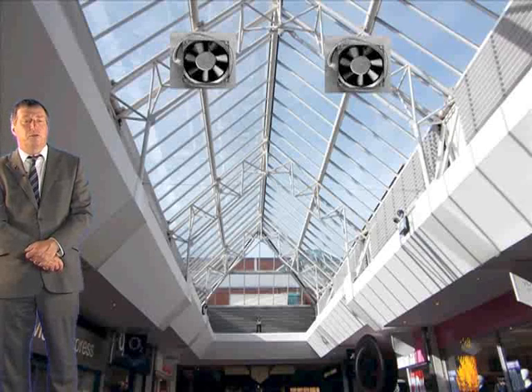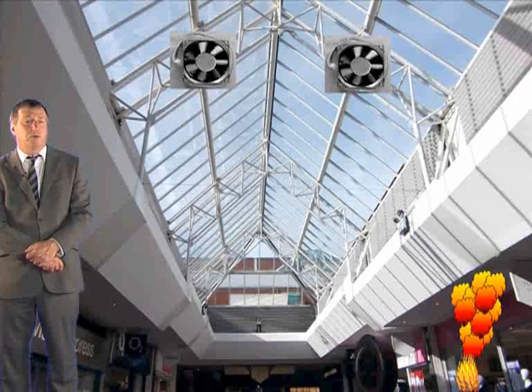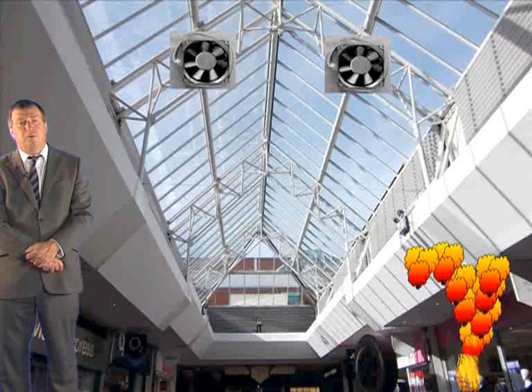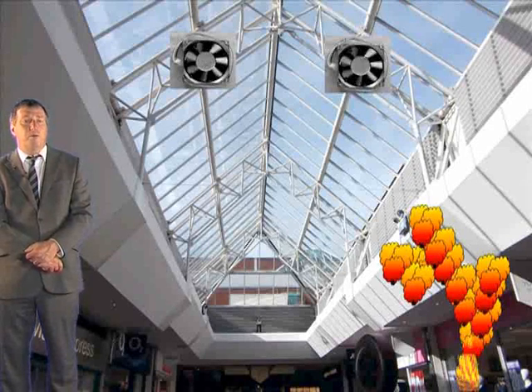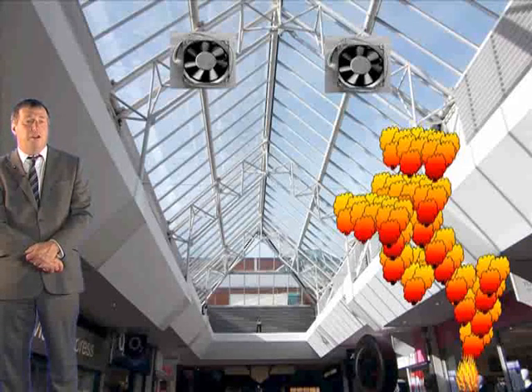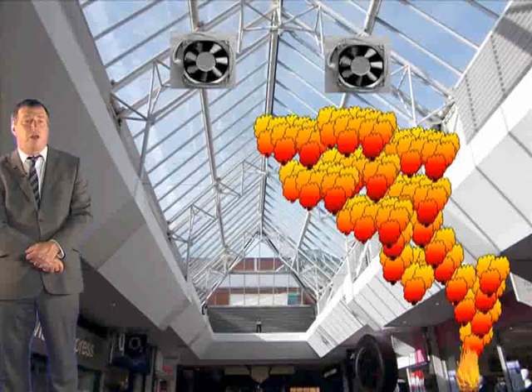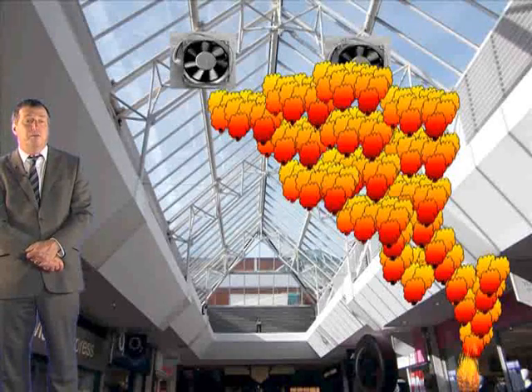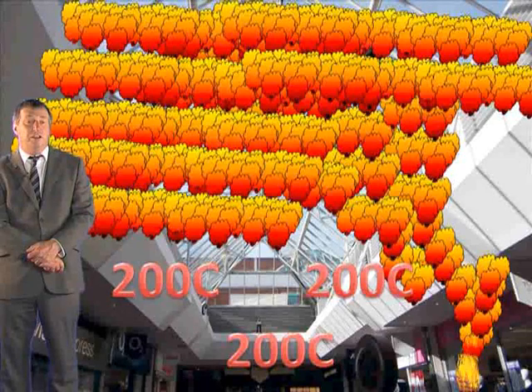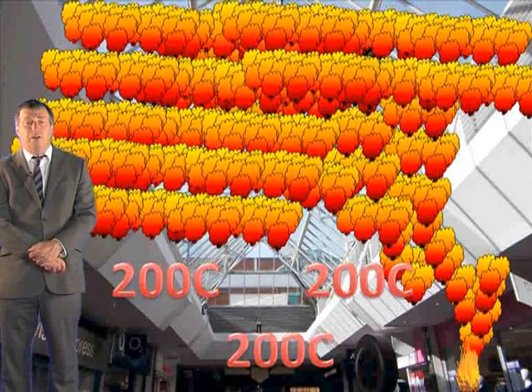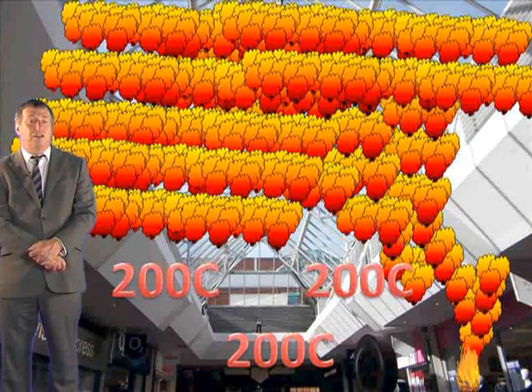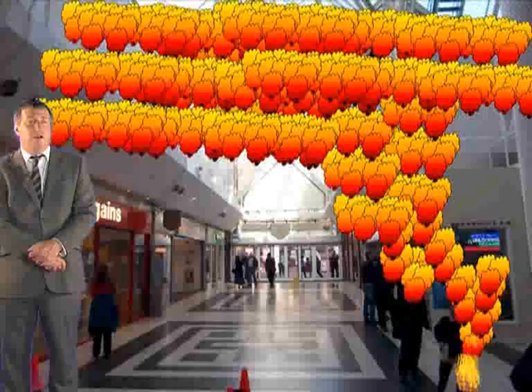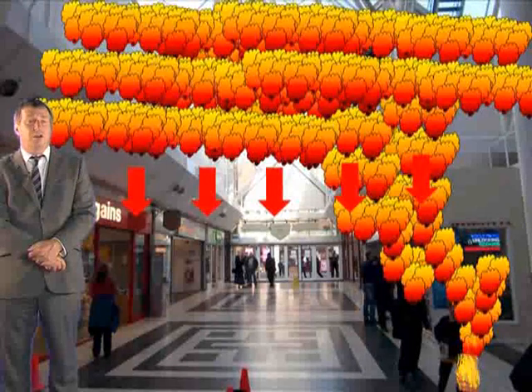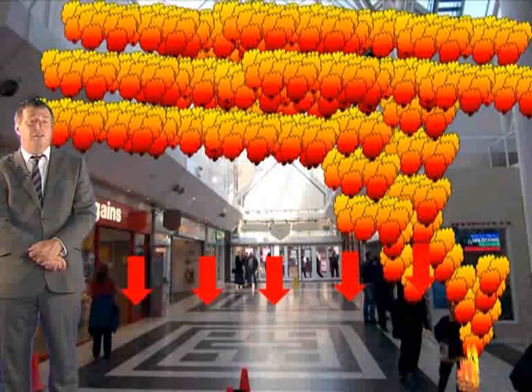As well as a lower acceptable temperature rise limit, there is a higher acceptable temperature rise limit. The upper limit depends upon the construction of the building and on whether or not people will be required to pass beneath the smoke layer when making their escape. If people will have to pass beneath the smoke layer, then the smoke layer temperature should be no more than 200 degrees C. This is often represented by a theta temperature rise of 185 Kelvin or 185 degrees C. And this would be the case where ambient air temperature is taken to be 15 degrees C. At 200 degrees C, people beneath the smoke start to feel pain where the heat radiates down onto them.